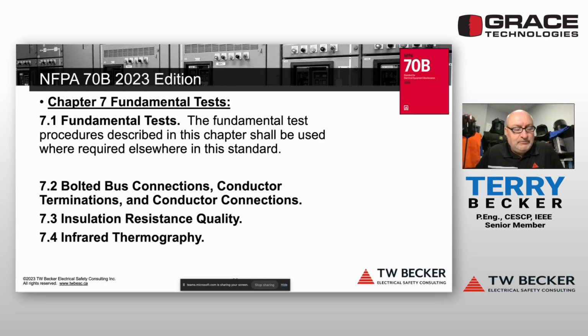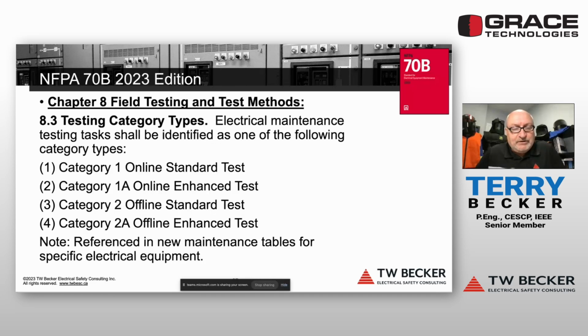Chapter 7, moving quickly through 70B. Fundamental tests: three things were identified - bolted bus connections, conductor terminations, and conductor connections, insulation resistance quality, and infrared thermography. These fundamental tests will be used where required elsewhere in the standard, as defined by inspection of electrical equipment later on.